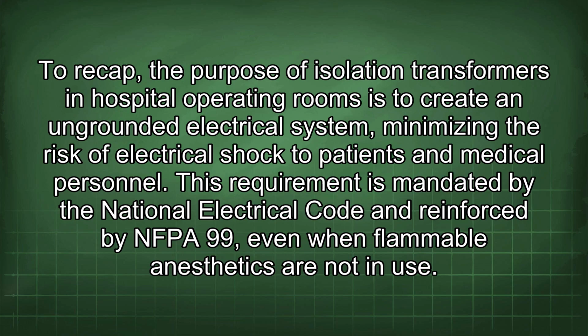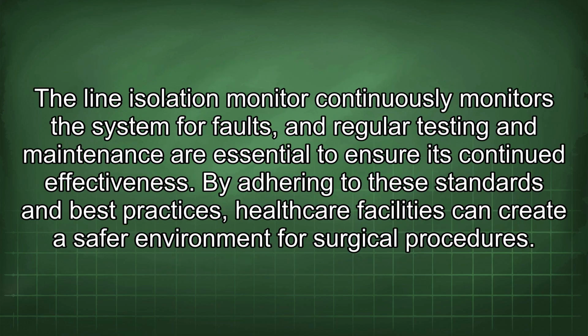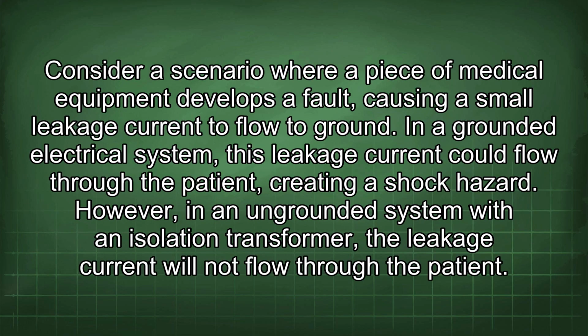The line isolation monitor continuously monitors the system for faults, and regular testing and maintenance are essential to ensure its continued effectiveness. By adhering to these standards and best practices, healthcare facilities can create a safer environment for surgical procedures. Consider a scenario where a piece of medical equipment develops a fault, causing a small leakage current to flow to ground. In a grounded electrical system, this leakage current could flow through the patient, creating a shock hazard.